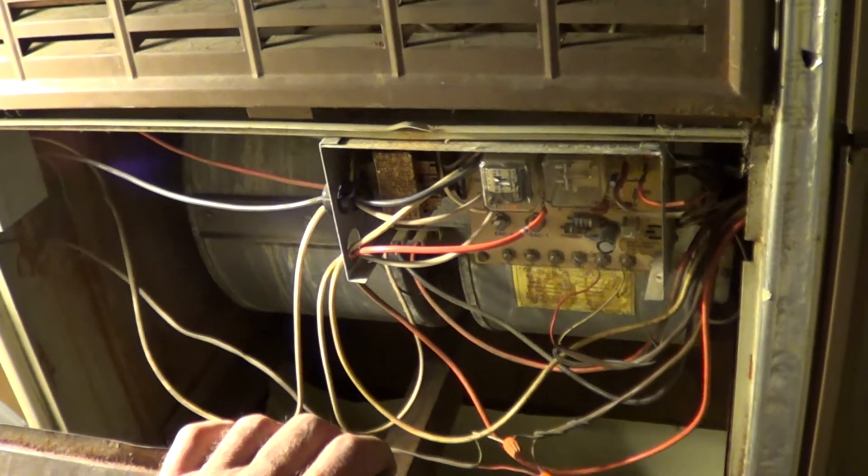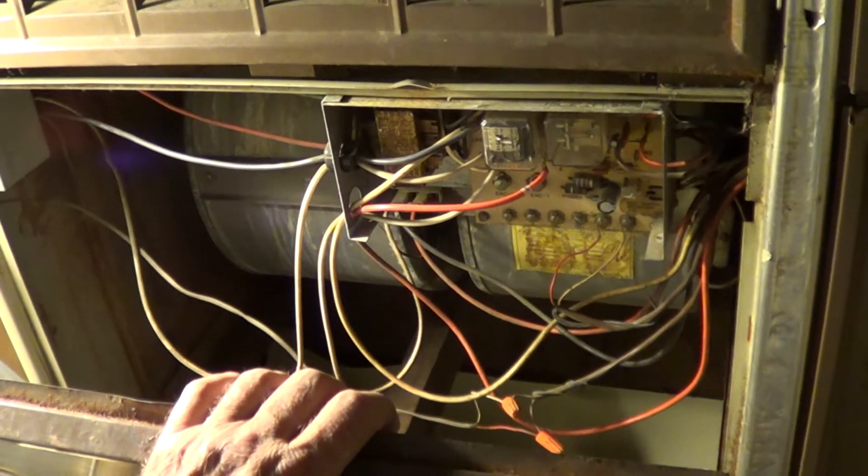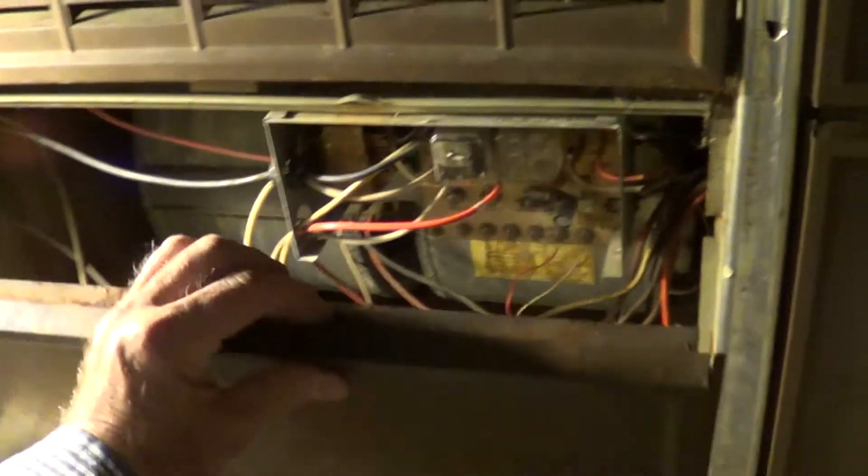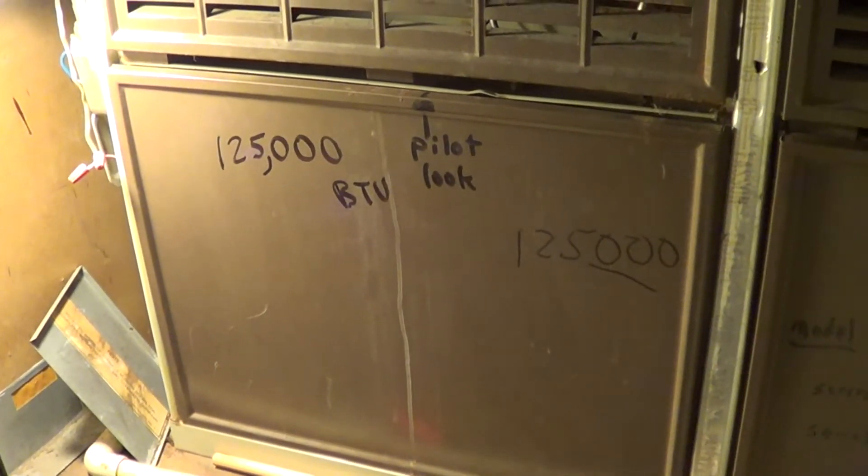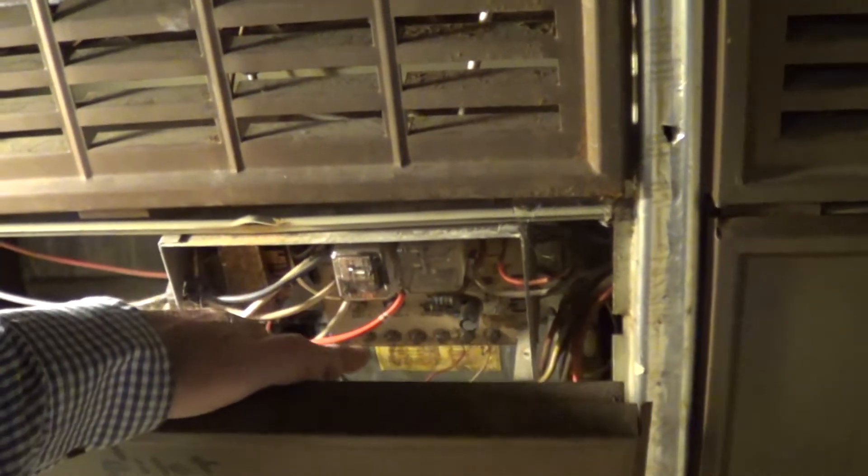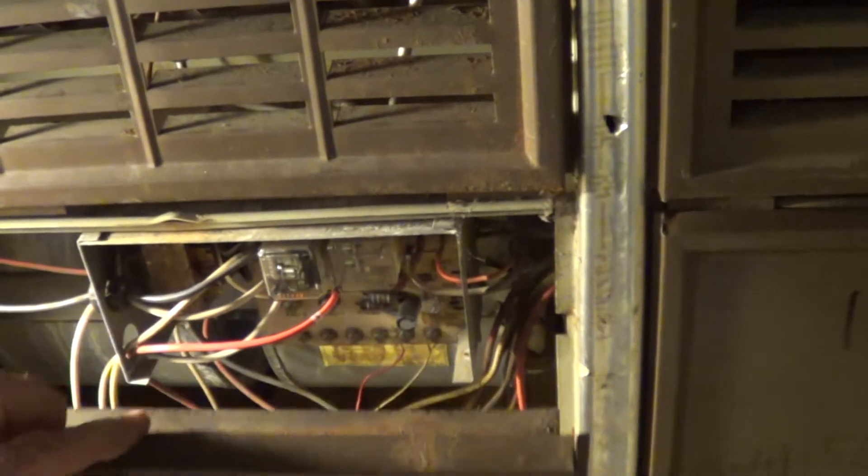I'll probably put one of the electronic ones on there, about anywhere between 40 to 80 bucks. But it used to kind of drive me nuts what was wrong with this thing. You'd run it, it would turn off, and then it would keep on running on low fan, and it's because this one relay was sticking. You just bang on the side and it'll turn off.